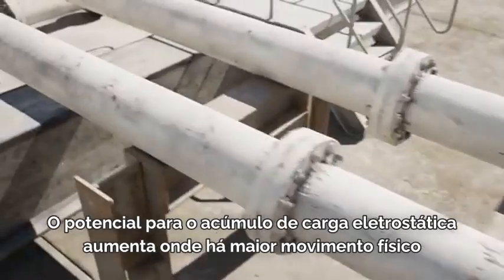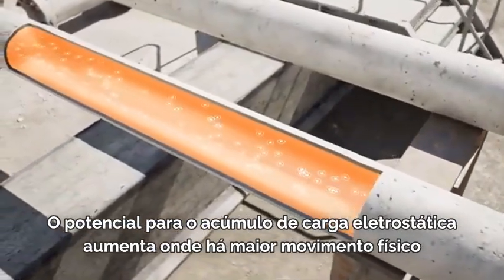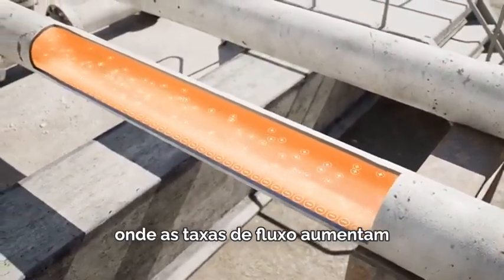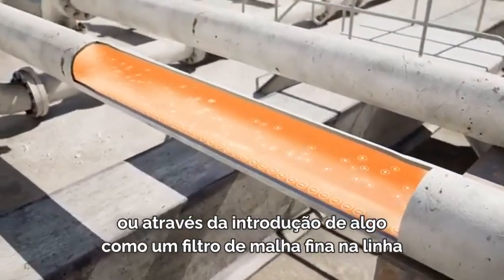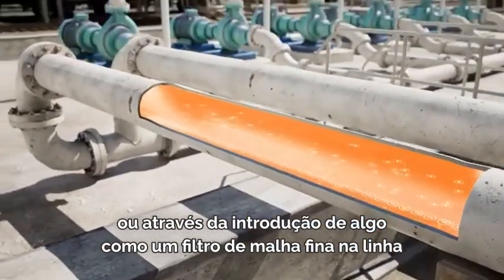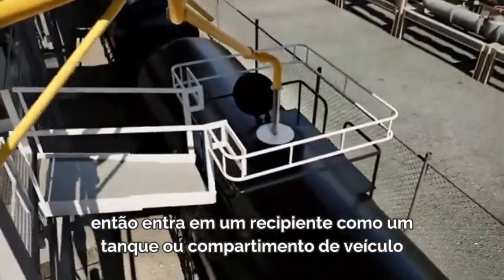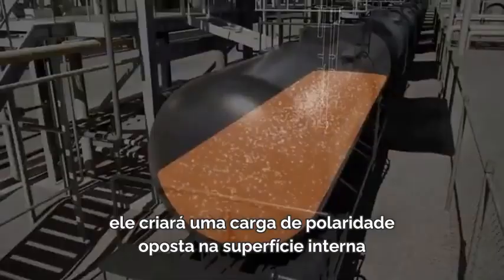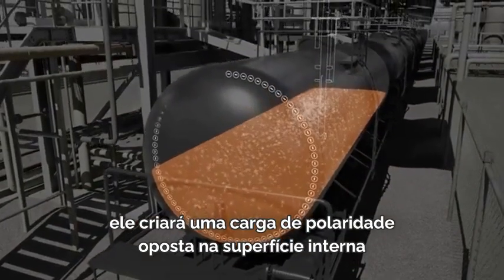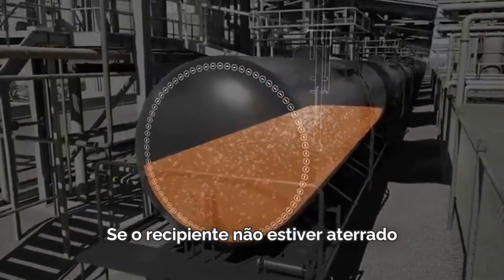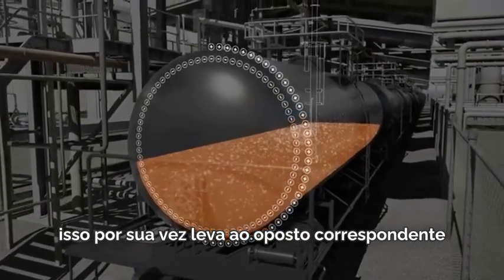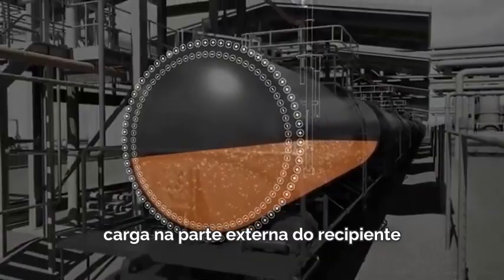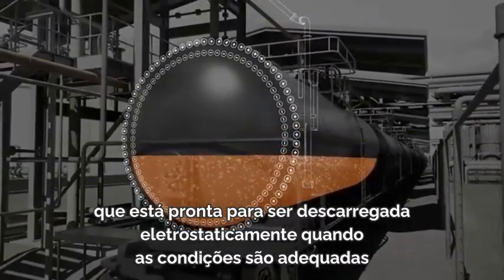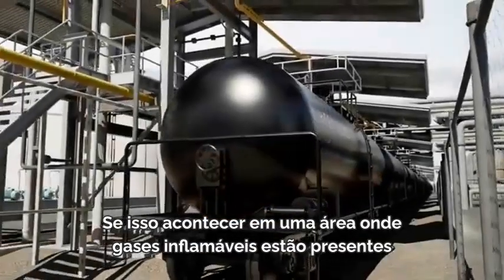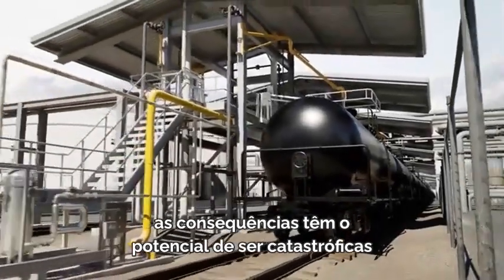The potential for electrostatic charge buildup rises where there is greater physical movement, in this instance where flow rates increase, or through the introduction of something like a fine mesh filter into the line. If the charged liquid then enters a container, such as a tank or vehicle compartment, it will create a charge of opposite polarity on the inside surface. If the container isn't earthed, this in turn leads to the corresponding opposite charge on the outside of the container, which is ready to be electrostatically discharged when the conditions are right. If that happens in an area where flammable gases are present, the consequences have the potential to be catastrophic.